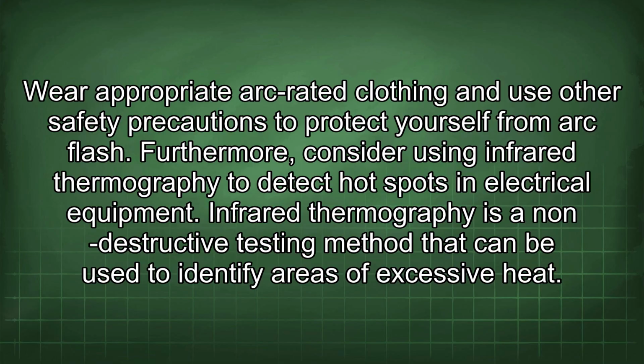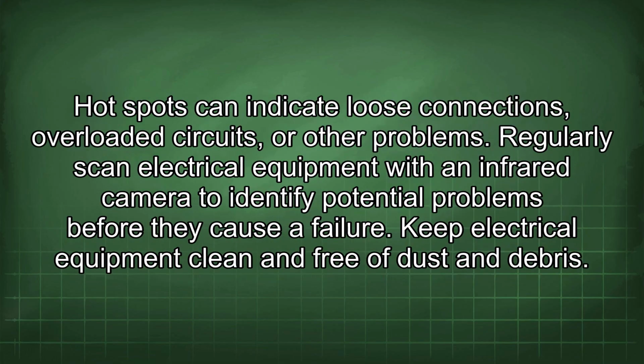Furthermore, consider using infrared thermography to detect hotspots in electrical equipment. Infrared thermography is a non-destructive testing method that can be used to identify areas of excessive heat. Hotspots can indicate loose connections, overloaded circuits, or other problems. Regularly scan electrical equipment with an infrared camera to identify potential problems before they cause a failure.